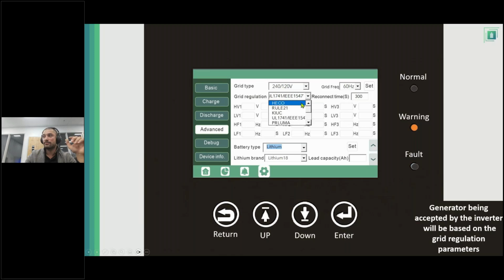And then the grid regulation is actually really important. I would recommend using Rule 21 or PR Luma. The reason is that, depending on how old the generator is, you might have some voltage or frequency fluctuations, and some of this equipment can be sensitive to that. So to open the range of voltage and frequency, we recommend using the Puerto Rico Luma setting or the Rule 21 setting, so that the inverter doesn't disqualify the generator, essentially. It's going to use those parameters.